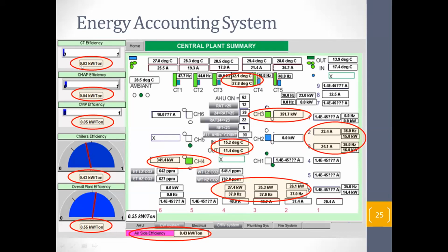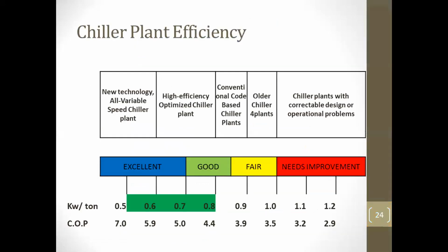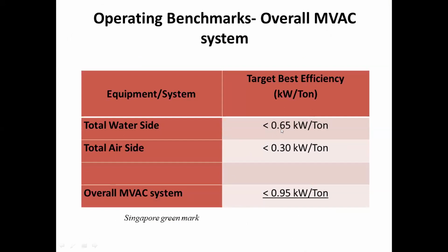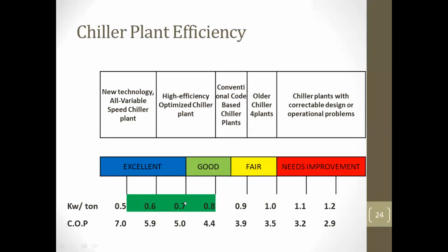Cooling towers, they operate at 0.03. Condenser water 0.04. Chilled water 0.05. Chillers, there are 2 chillers operating at that time, 0.43. And overall plant efficiency is 0.55. Hope you can remember, here, 0.65. And ASHRAE, anything below 0.7 is excellent. So they are operating somewhere here.